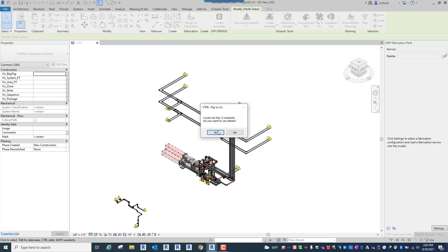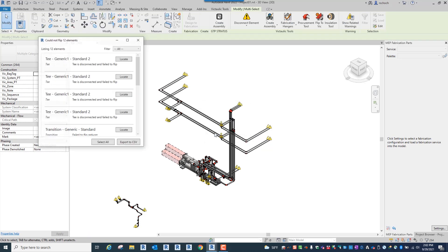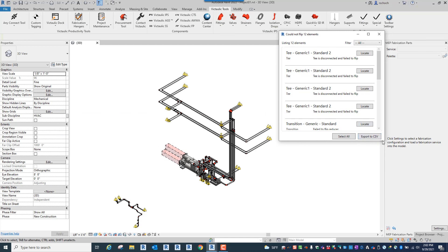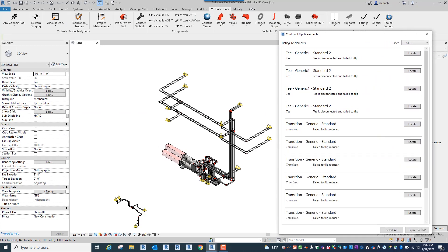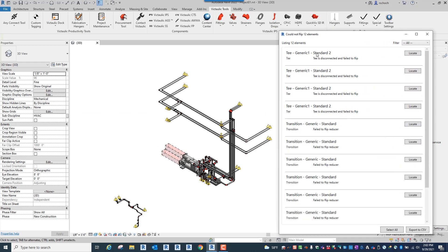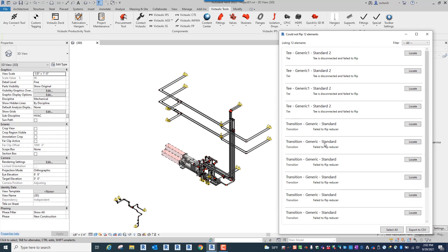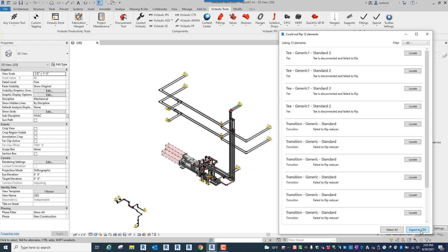So you do see we do have some issues so we can click yes and then here what's nice is this error report gives you an idea, it shows you what issues happened. So it looked like it had some issues with transitions which is fine and a couple tees. If I want to locate any of these elements I can do that by clicking the locate button. I can select all of them and apply some data to them maybe something that's filterable, or I could obviously just change their display or their color in this view and then go back and find them. I can isolate them in the view. I can export this data out to a CSV if I later want to go back. The CSV will include the ID of the element so you're able to coordinate that and track that back.